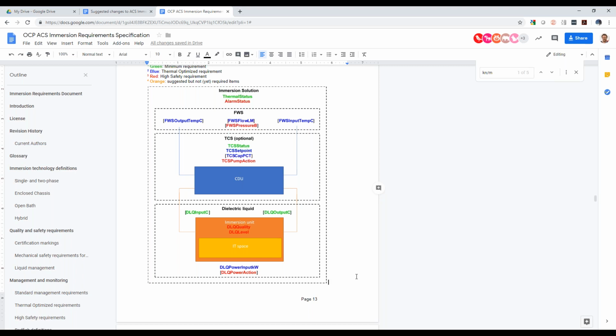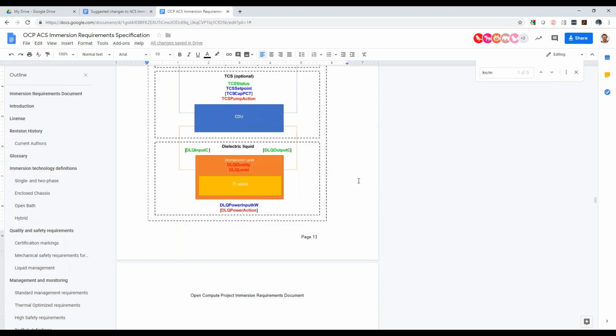With the CDU, then within GRC's system, since you referred to the GRC system earlier, they would have an FWS input directly to their CDU, which is a shared CDU connected to their immersion unit - without a CDU inside, that's correct. That would give you multiple dielectric liquid units within that immersion system, the immersion system being the one sharing the CDU.